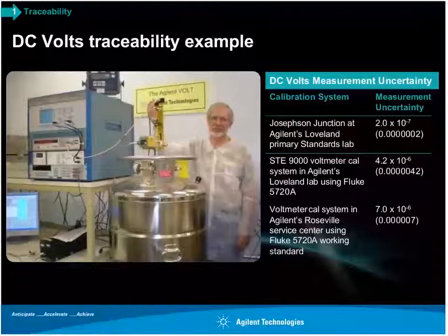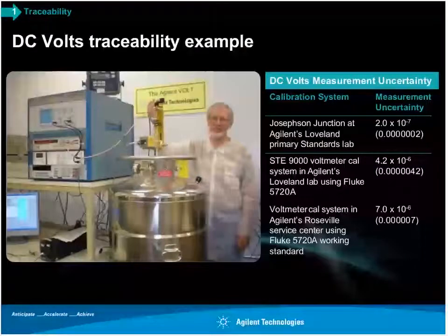The point I wanted to make here is if you take the Josephson junction and you use that to calibrate the voltmeter cal system that we use for other voltmeters, and there we're using a Fluke 5720 as our main base instrument. You can see the measurement uncertainty there. It's very, very good, but it's not quite as good as what that Josephson junction was. And then if we were to use that very voltmeter cal system to calibrate yet another one, in fact, the very same system, just a different one, you can see how the accuracy begins to degrade each time you change the comparison.